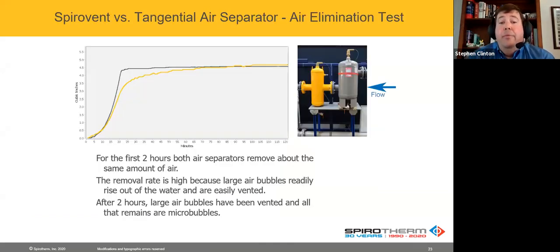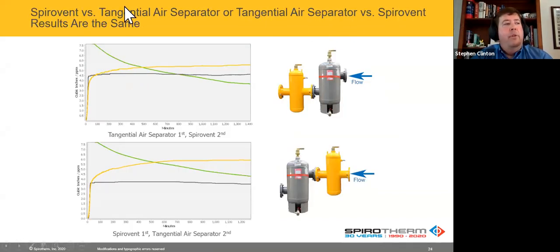We want to share that data with you, because what we found was, all right, the first unit, the traditional air separator, is able to see the big bubbles first. So it's able to remove them each pass, and then we're removing air as well. So for the first hour, we're both removing air, and then it's still happening a little bit in the second hour. But watch what happens when we get past about that first hour and a half or 2 hours. The traditional separator basically flatlines, and we continue to remove air. The difference is even more significant when you look at what's happening if we get first crack at the air.